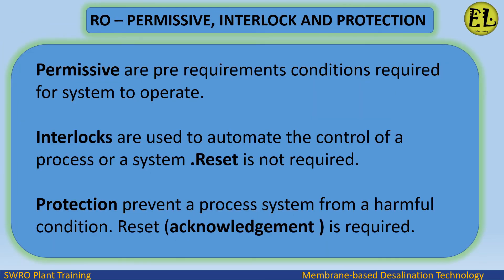Summary: Permissives are pre-requirement conditions required for the system to operate. Interlocks are used to automate the control of a process or system — reset is not required. Protection prevents a process system from a harmful condition — reset and acknowledgement are required.